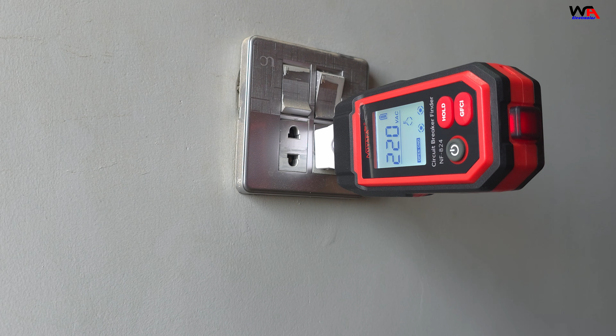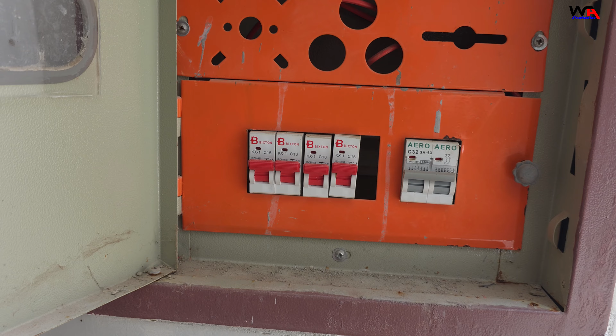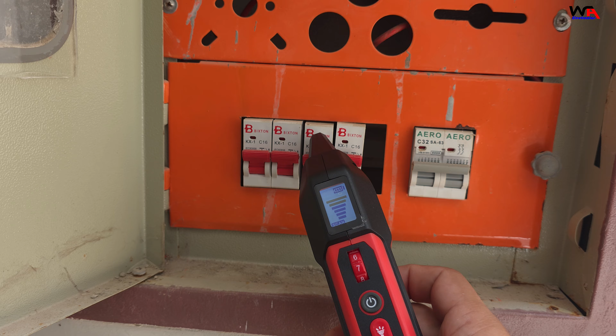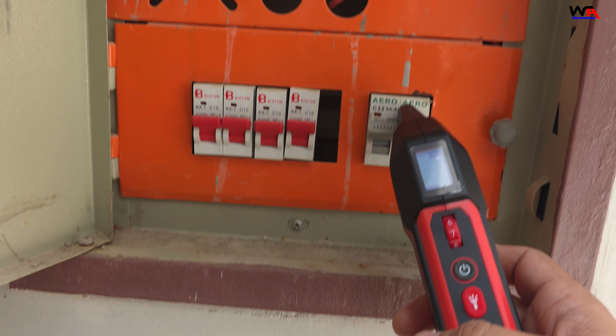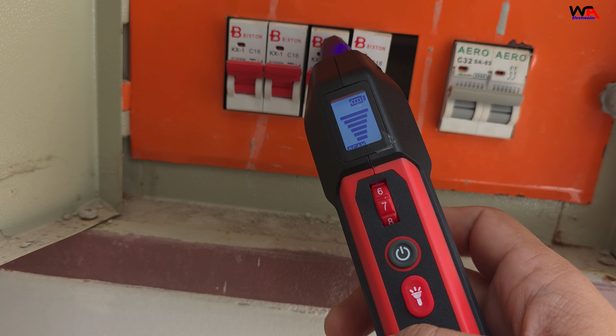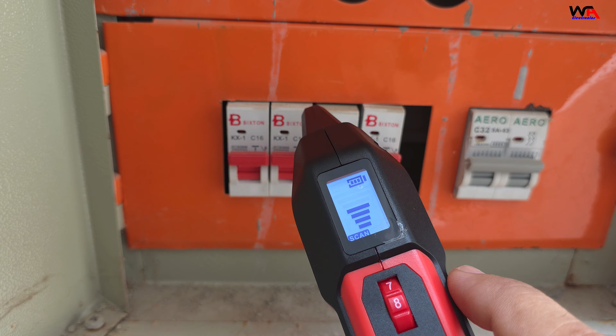Real-world testing. Now comes the most important part. Let's see how well it performs. First, plug the transmitter into the outlet you want to identify. Next, walk over to your electrical panel with the receiver. As you move the receiver across each breaker, it begins detecting the transmitted signal. You'll notice the receiver starts beeping. As you get closer to the correct breaker, the beeping becomes faster and stronger, while the signal indicator increases. Once you've confirmed the strongest signal, you've located the correct breaker. This saves a huge amount of time compared to switching breakers one by one.